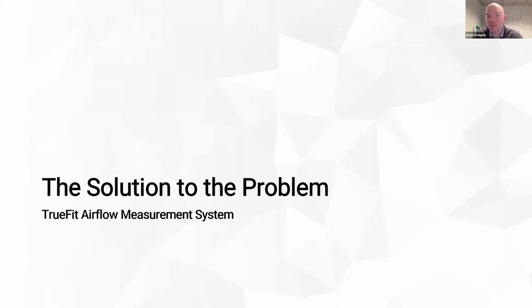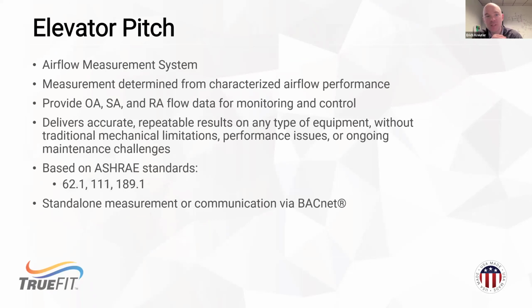So now we have a little background. Let's talk about the solution to the problem. So, TrueFit Airflow Measurement Station. It is a system of components that provides reliable and repeatable outdoor supply and return airflow measurement for monitoring or integrated control. The measurement itself is based on ASHRAE standards, namely that 111 standard.